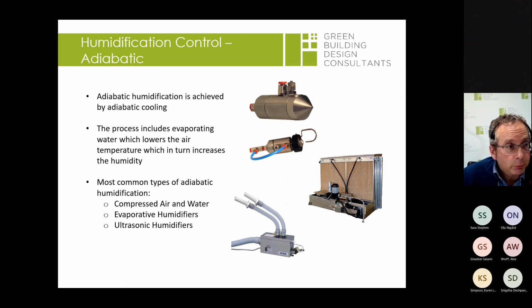There are various types, but really you can either have a tray of water that sits at the bottom of your air handling unit, and then using vibration and oscillation with pneumatics, it vibrates the water and causes the particles of water to separate, and as the airstream goes across it, it picks up the moisture that way. Another option is the picture on the right here, where we spray our water through a filter medium, and it becomes quite wet. As the air goes through it, it cools down and picks up the moisture.